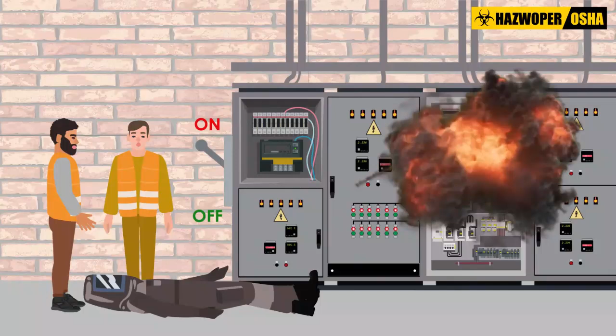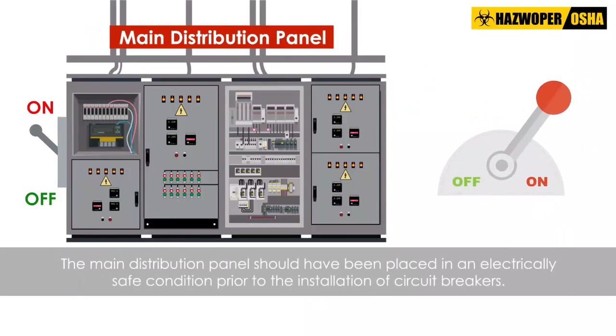OSHA's investigation into the incident concluded that the arc flash and subsequent injury could have been prevented by adhering to basic electrical safety principles. First and most importantly, the main distribution panel should have been placed in an electrically safe condition prior to the installation of circuit breakers.